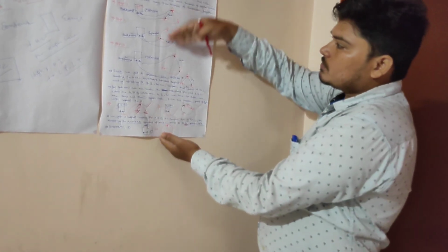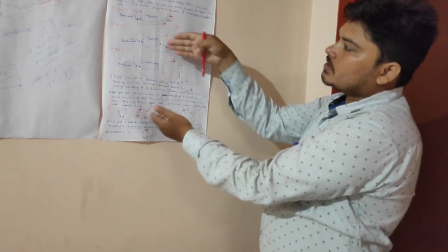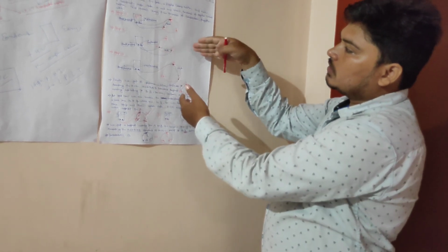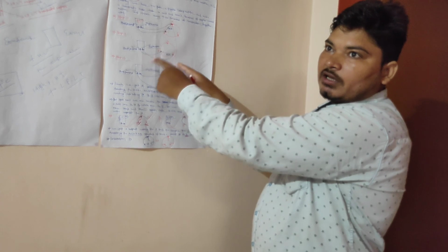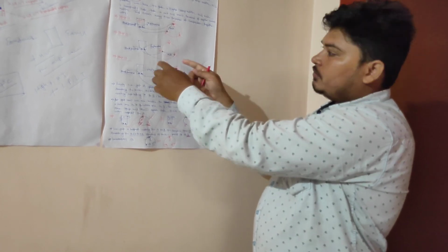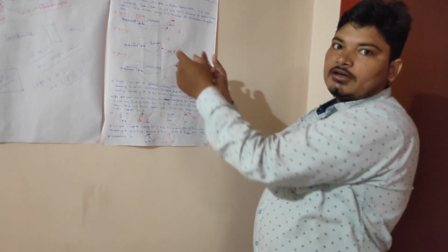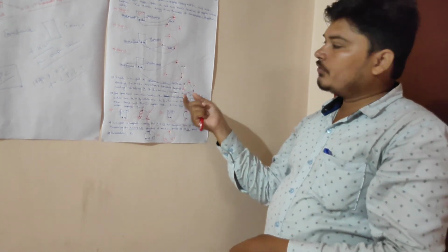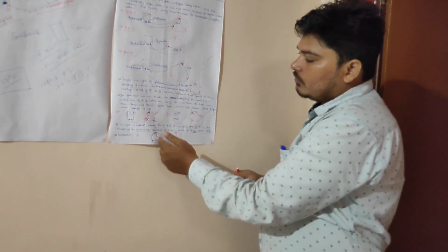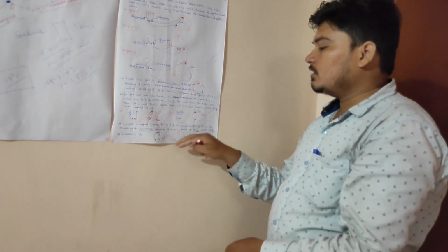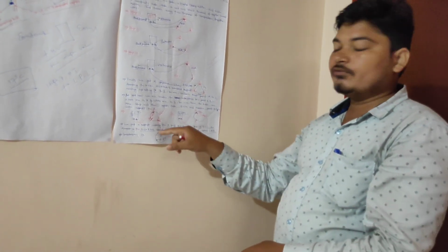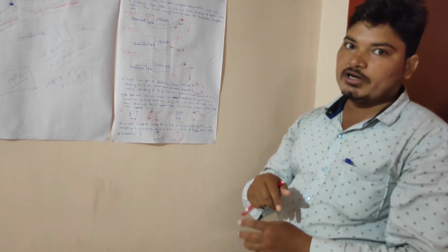By the help of this process, by the help of digital clamp meter continuity mode, and making every 2 electrical terminals, between electrical terminal resistance value reading, we can justify which one is exact common point, which one is exact running point, and which one is exact starter point.